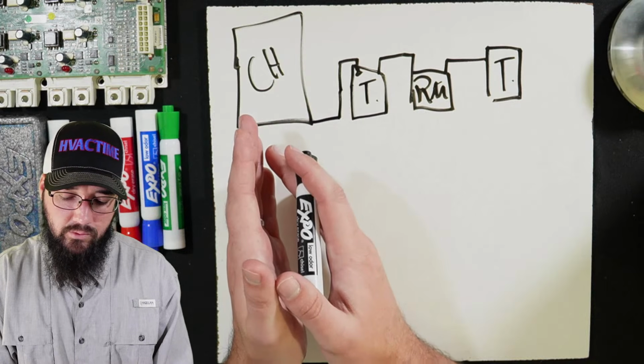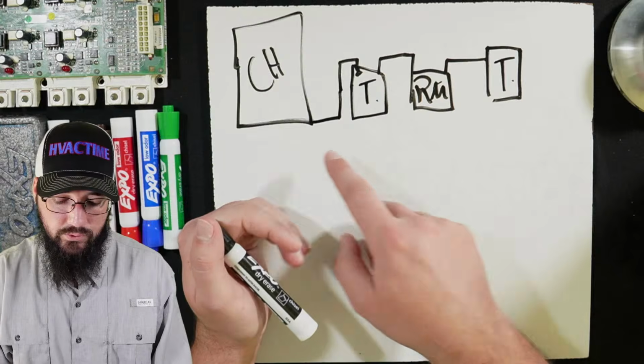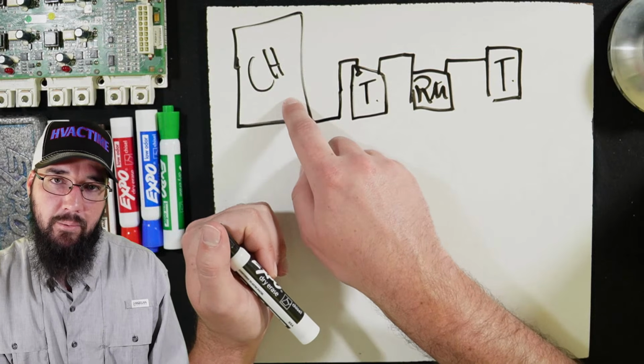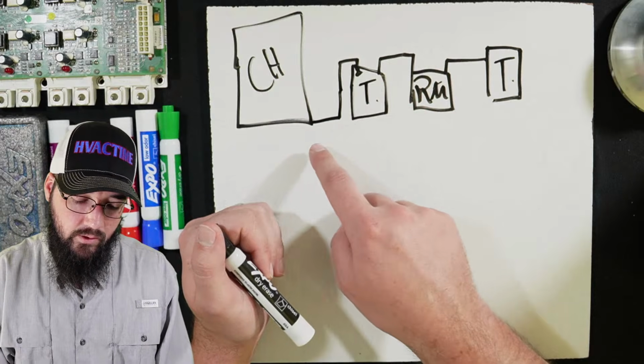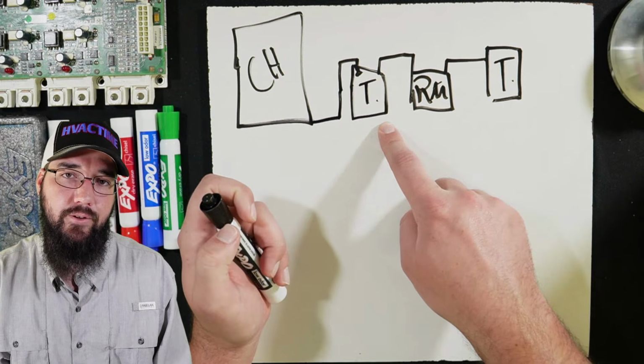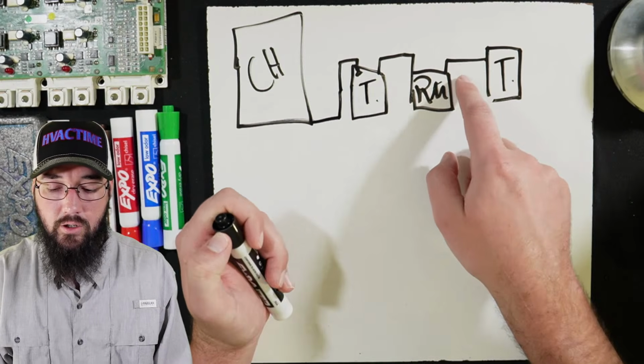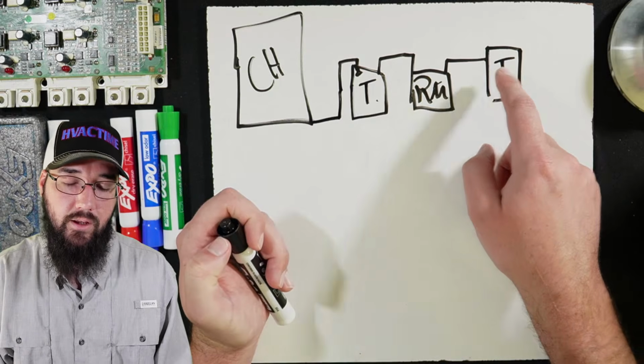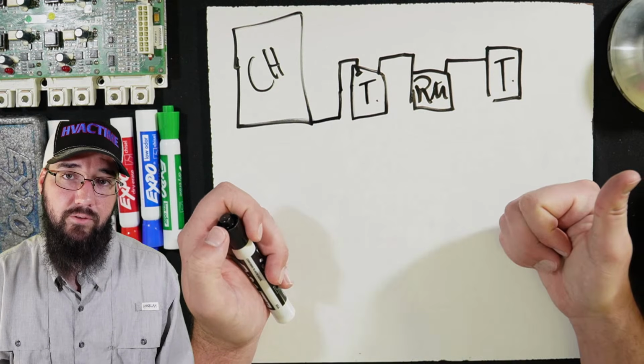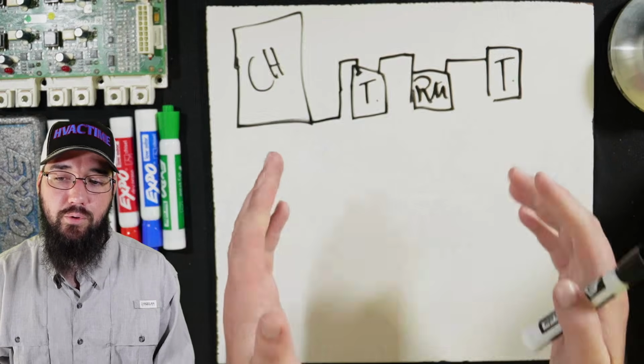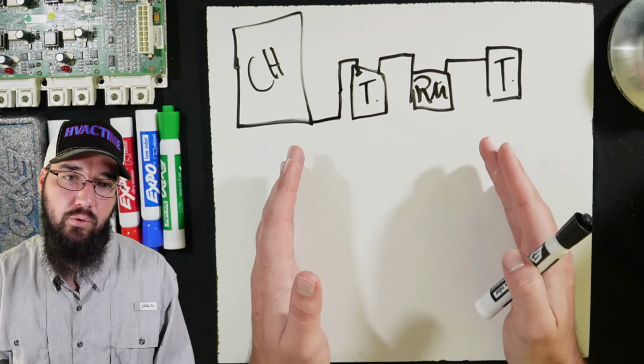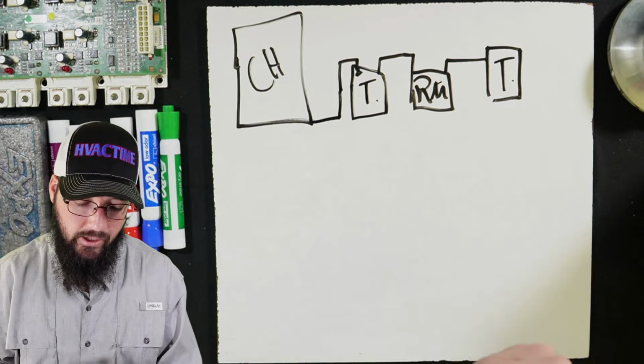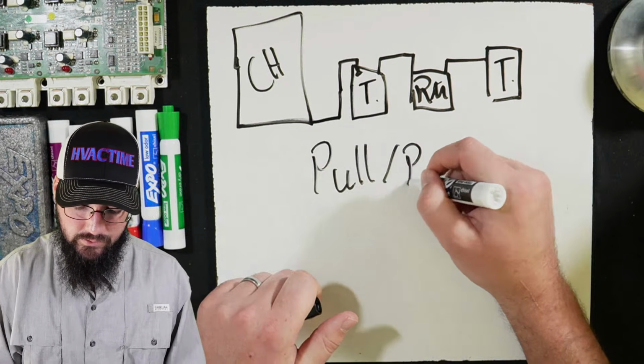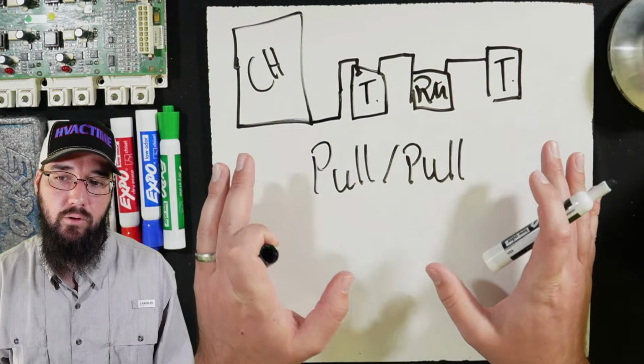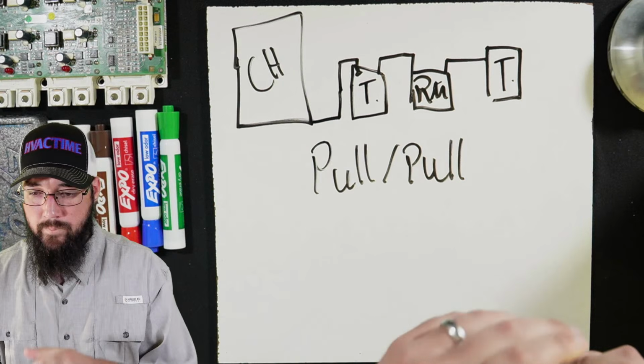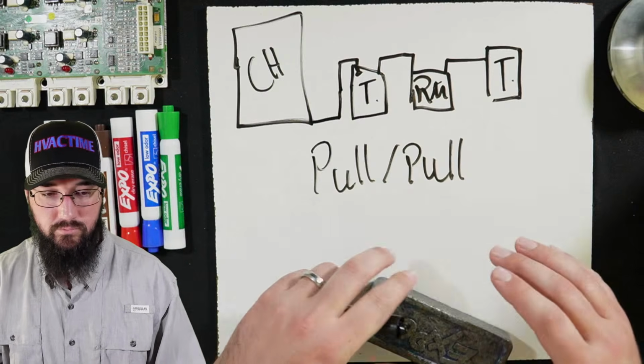So ultimately, that's the high levels. We don't risk adding contaminants to the chiller by recycling. We also get to capture all of our liquid refrigerant. And if you use a subcooler on the discharge side going into your vapor tank, it is an extremely fast, effective method. So those are your primary advantages of why pull is worth your time. And I am saying pull, just so we're clear. Okay, this is a pull method. And I can 100% vouch, it works really well.